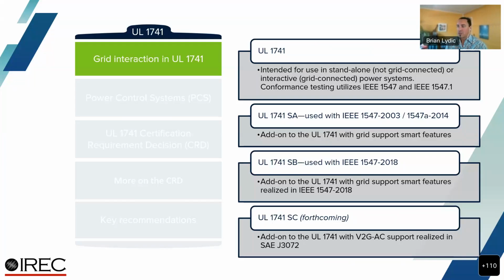But the reason SA was created was because we didn't yet have IEEE 1547-2018, and so this was a way to get smart inverters to market earlier than waiting for IEEE 1547 to be updated. There weren't actual requirements for smart inverters in 1741 SA, so they relied on what they called SRDs, or source requirements documents, which would have been found in Rule 21 in California, and for Hawaii, HECO's Rule 14H. Those served as the basis of the requirements.